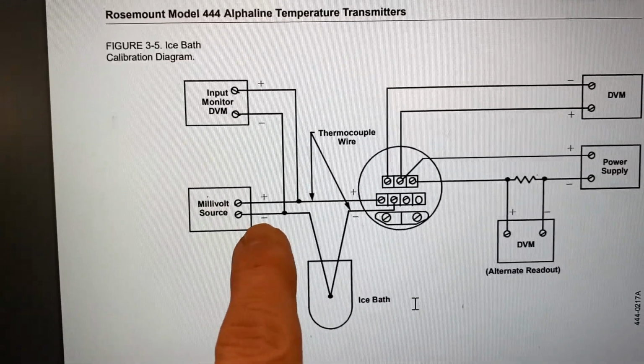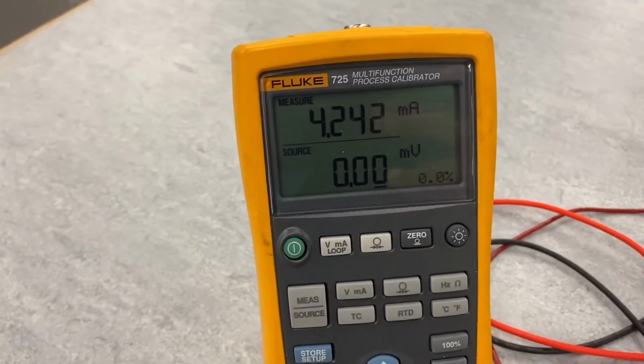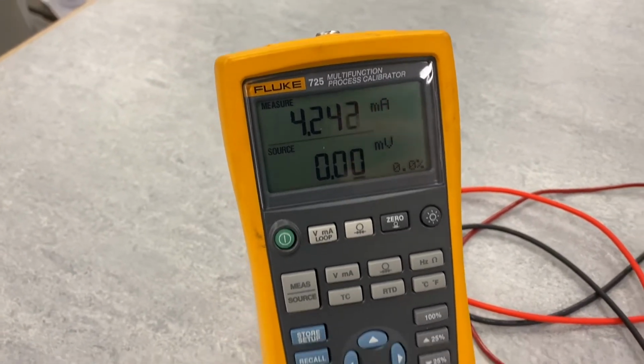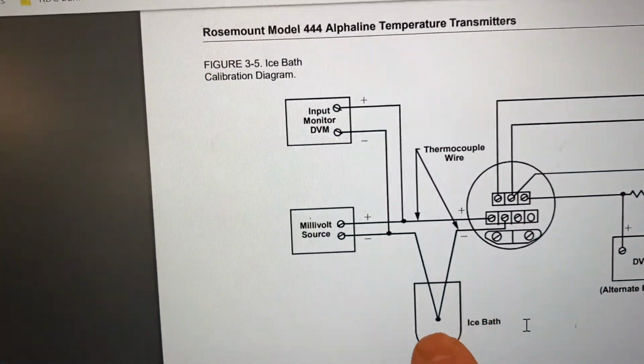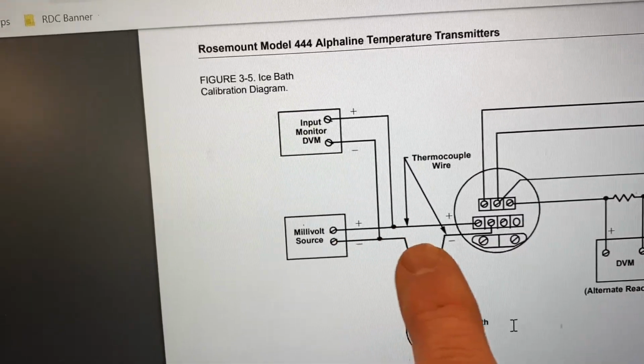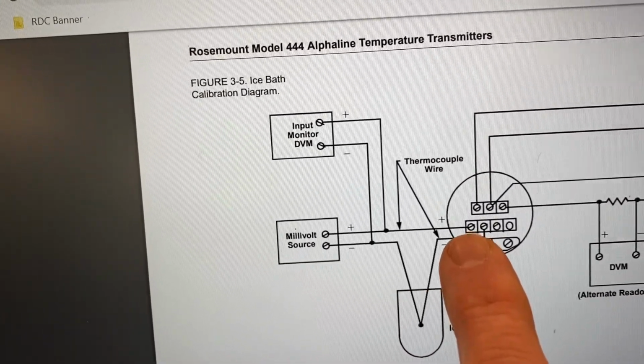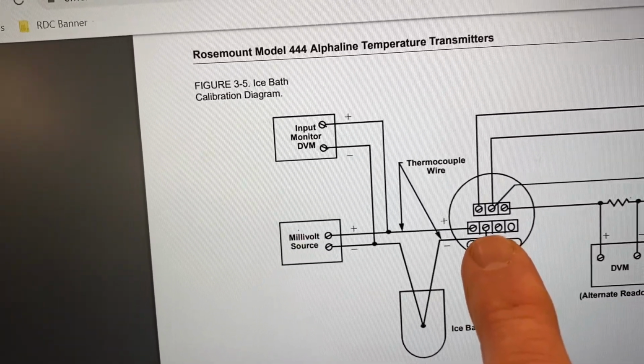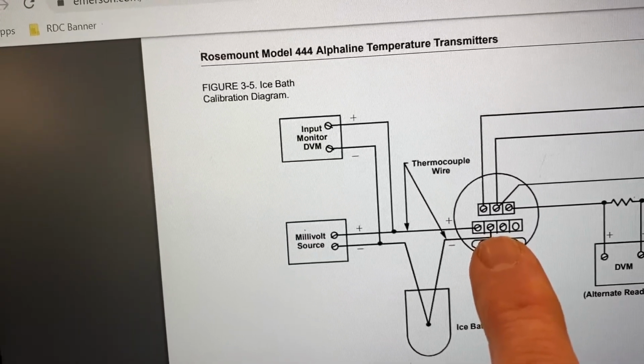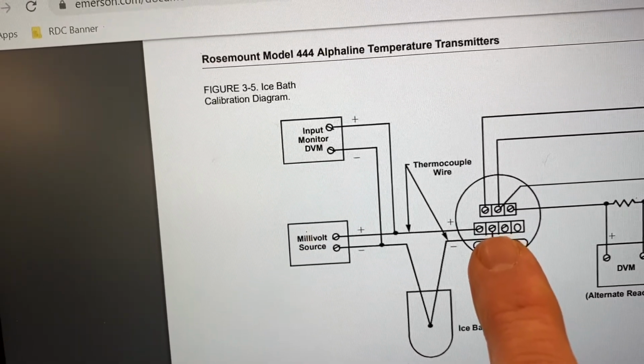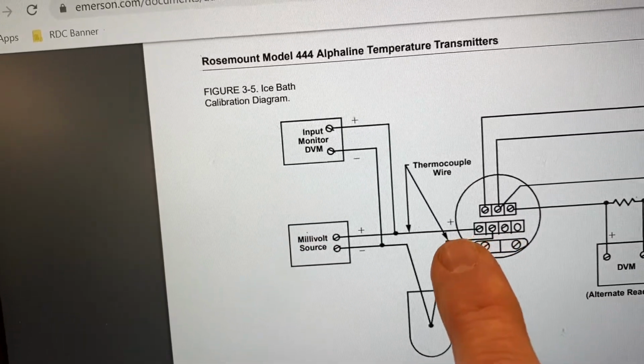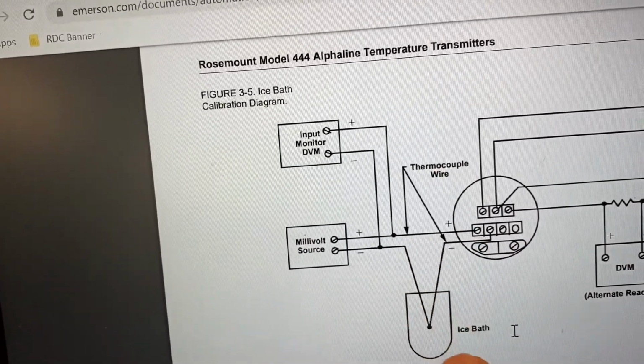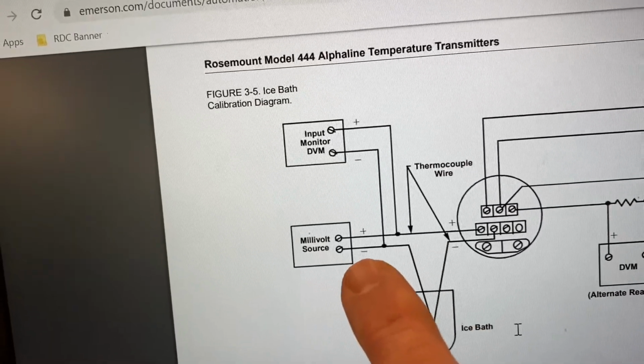We need to have a millivolt source. The millivolt source in our case is going to be our Fluke 725 multi-function process calibrator. So I have that connected up. You can see here the positive of the meter goes to the positive of the millivolt input on the transmitter, and the negative of the millivolt input, or the thermocouple input on the transmitter, goes to the negative lead on the thermocouple down to the ice bath, and then the positive of the thermocouple goes to the negative input on the millivolt source.